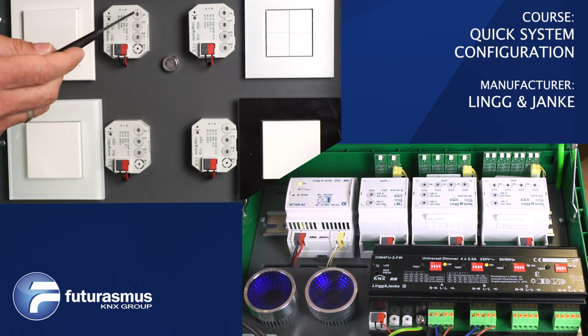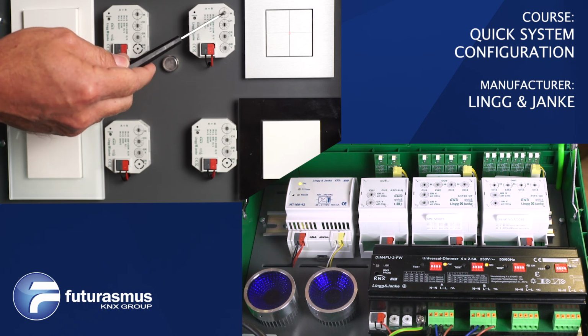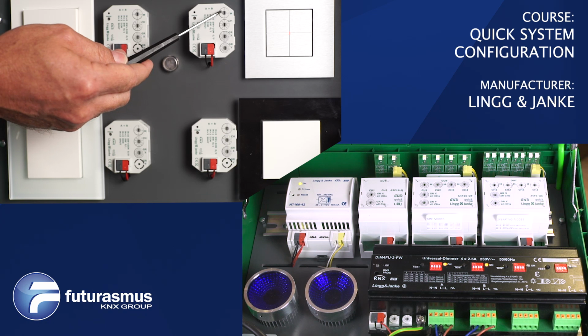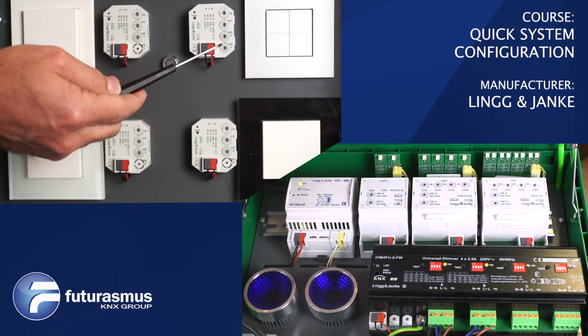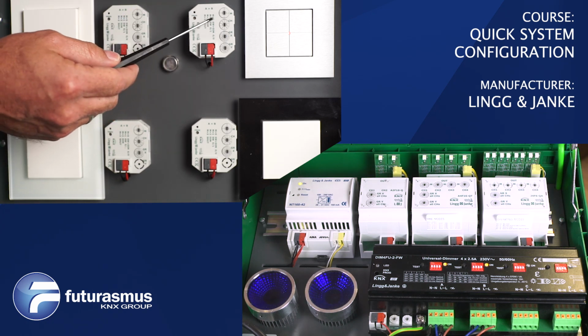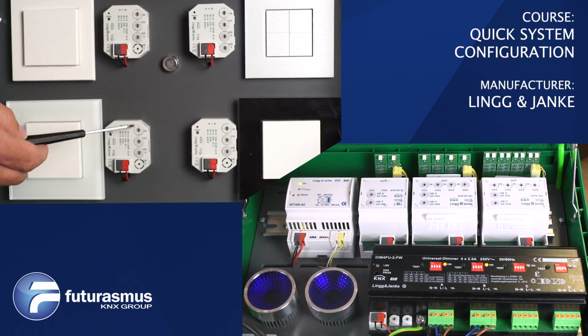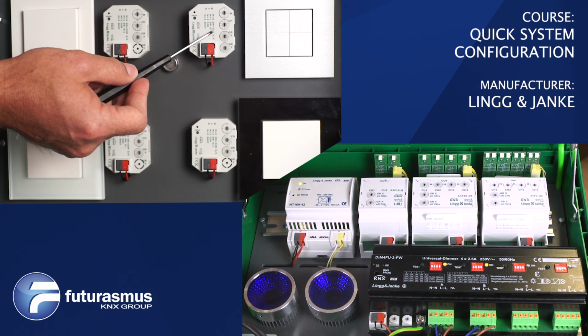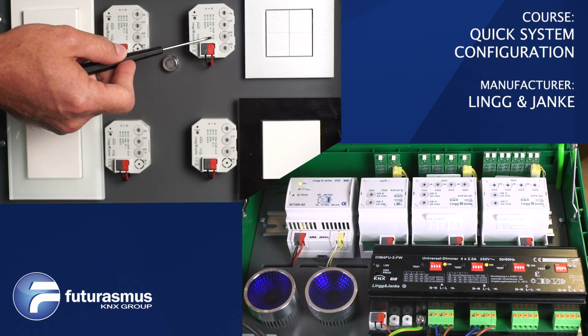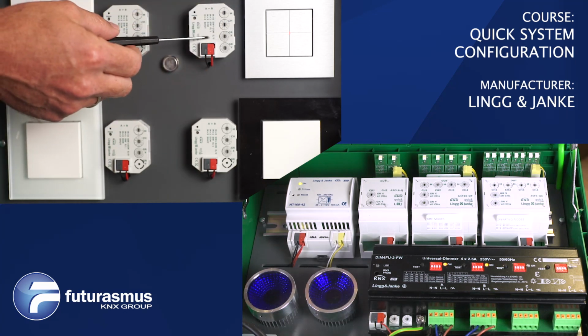Now, there are different types of coding switches. Let's have a look at this one, where we have the M for mode, CH for channel, and then the group X and the group Y. The mode is written on the device, so it's easy, you don't need to go into a manual. You can just check on the device what function you want to do. With M0, you've got switching and dimming, and you will always send a 0. So independent of which button you press, it will send a 0.